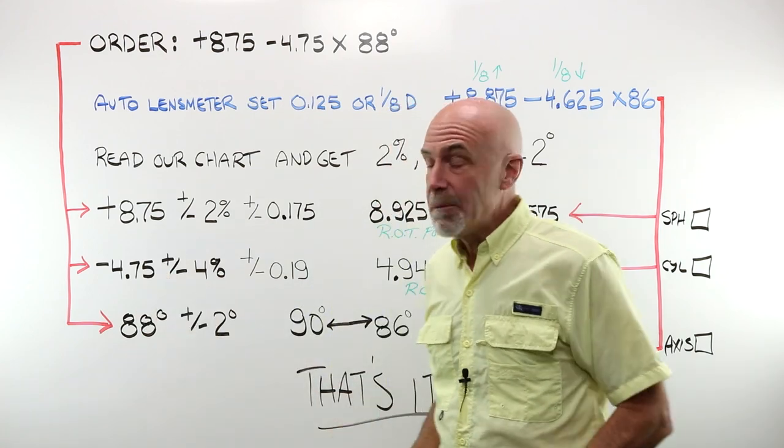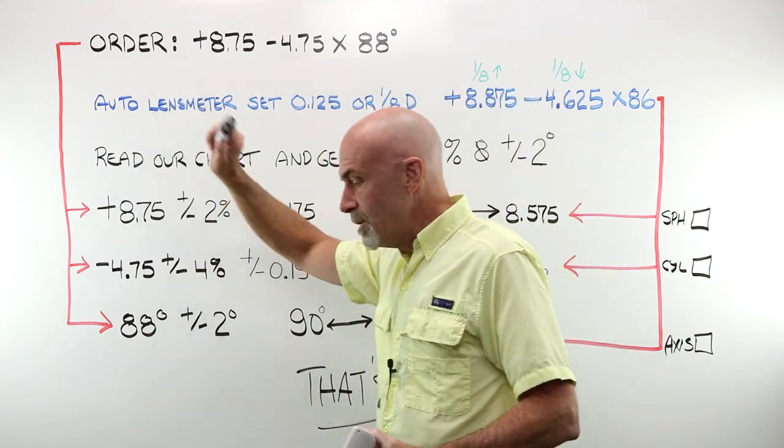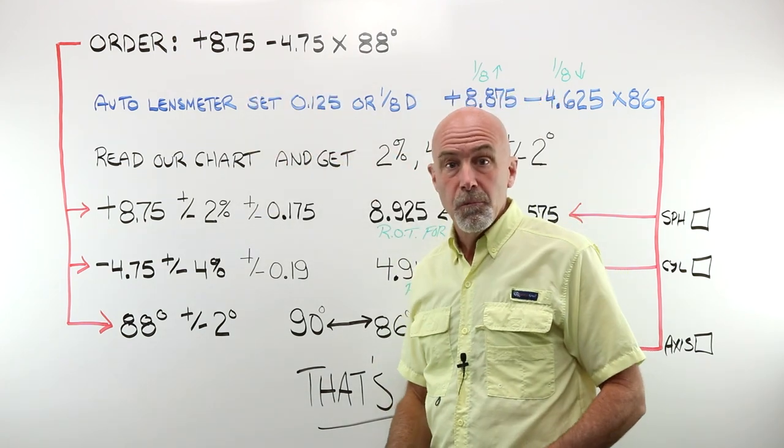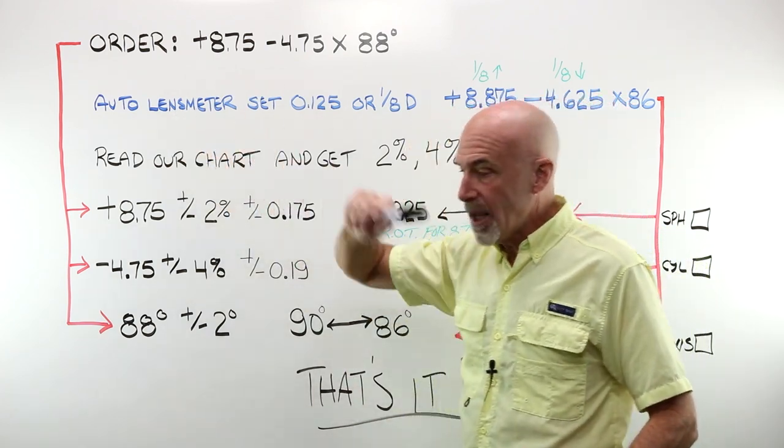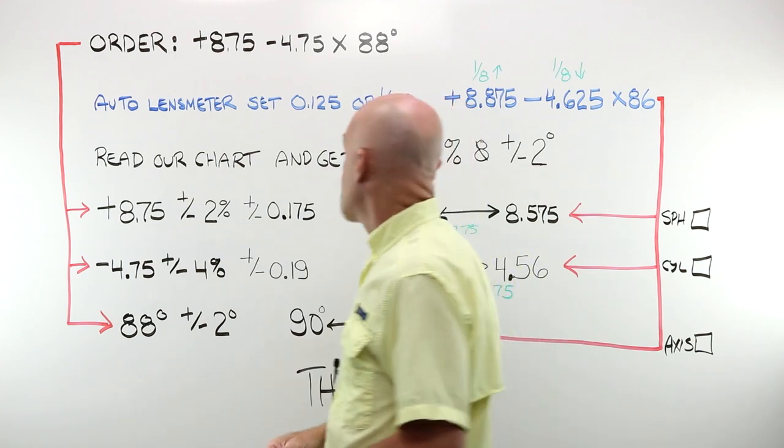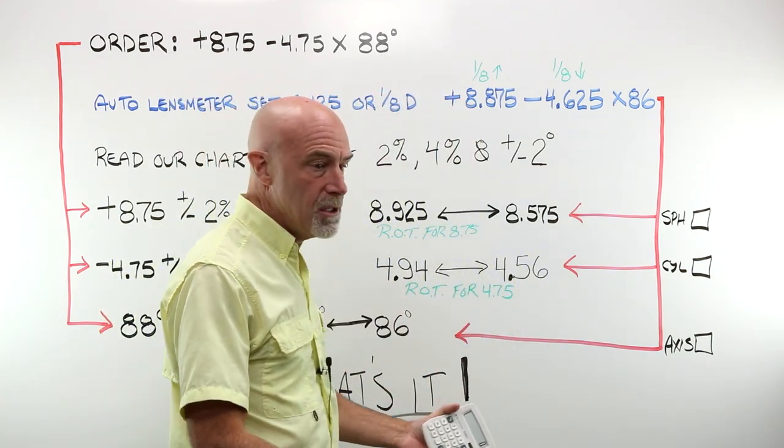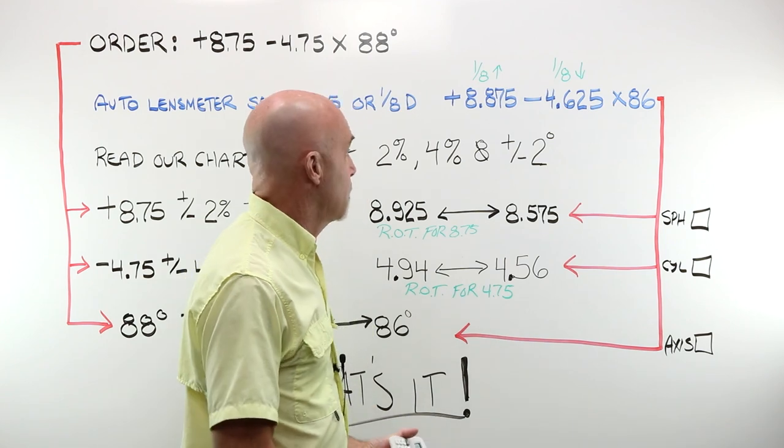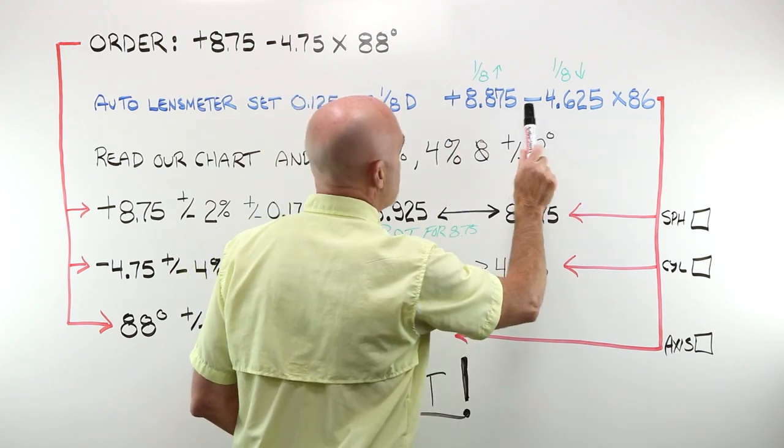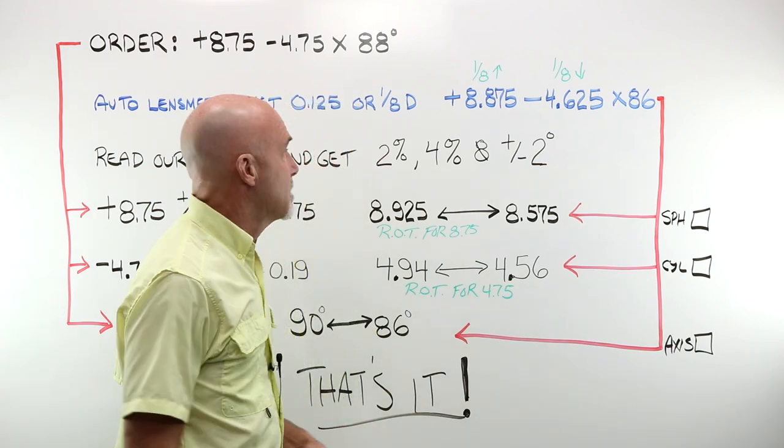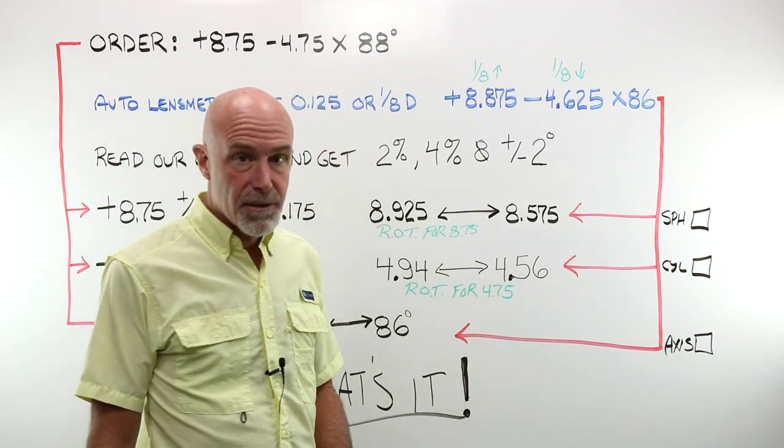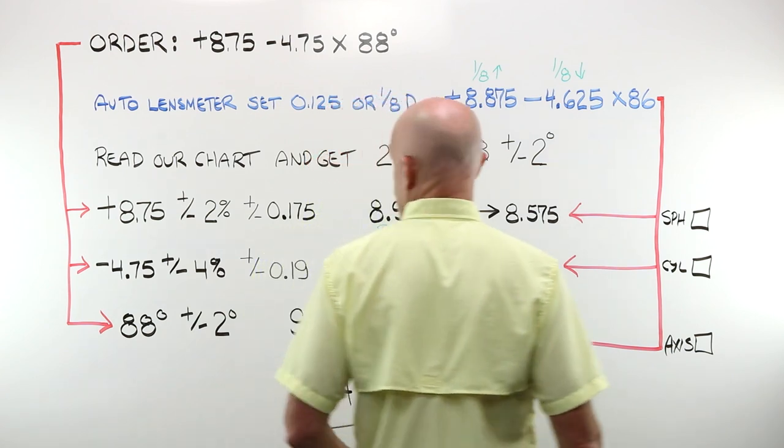All right, I'm going to run through two case examples. This is our first one. You ordered plus 875 minus 475 at 88. Where you work, you are extremely fortunate. You have a beautiful high-end auto lens meter set to read to the nearest 0.125 or eighth diopter step. You put the glasses into the auto lens meter, line up everything just like you should. You hit the print button and the ticket prints out and it says it's a plus 8.875 minus 4.625 at 86. It is one-eighth of a diopter strong in the sphere and one-eighth of a diopter weak in the cylinder. Not terribly unusual, actually.